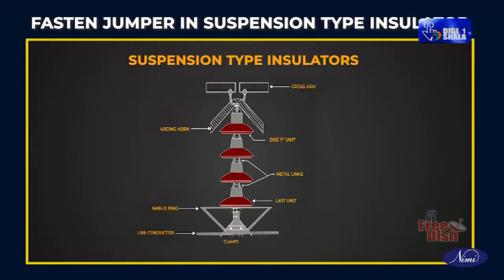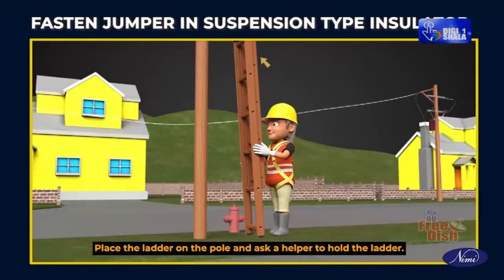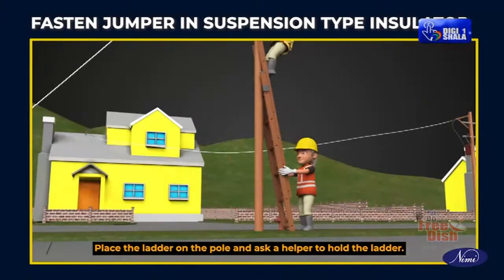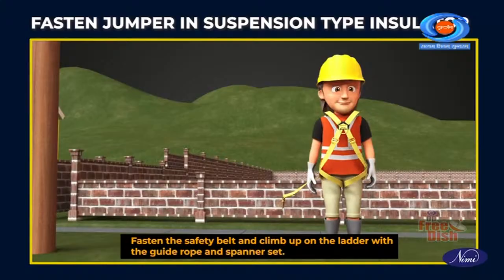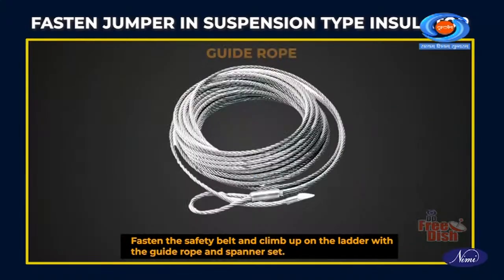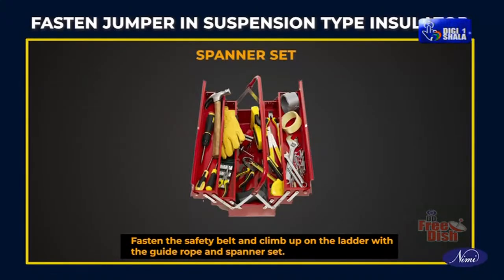Our third task is fasten the jumper in suspension type insulator. Check the tools and materials for its good condition. Place the ladder on the pole and ask a helper to hold the ladder. Fasten the safety belt and climb up on the ladder with the guide rope and spanner set.